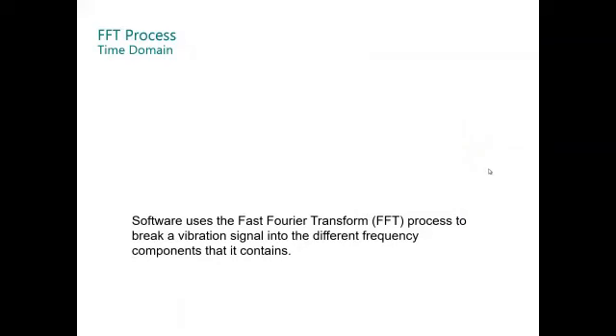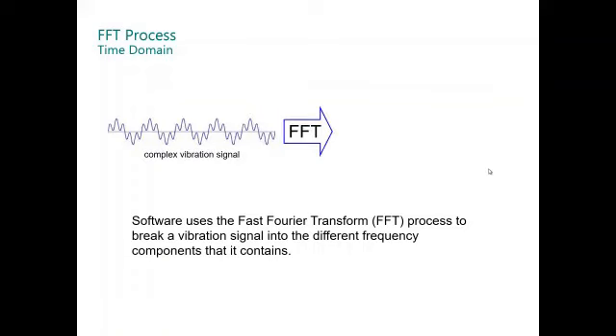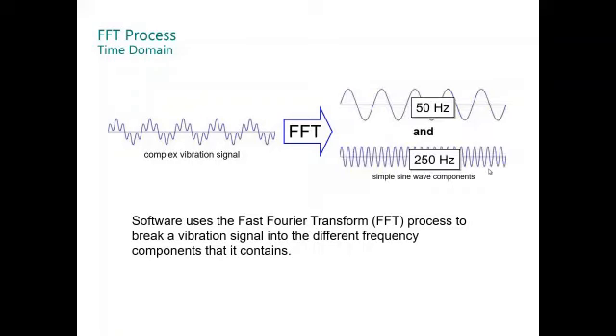One of the signal processes is using the FFT or Fast Fourier Transform. This converts the time domain into frequency domain and is called spectrum. You have a complex vibration signal. Using the FFT, it's converted, in this case, into two components: one component at 50 hertz and the second at 250 hertz.